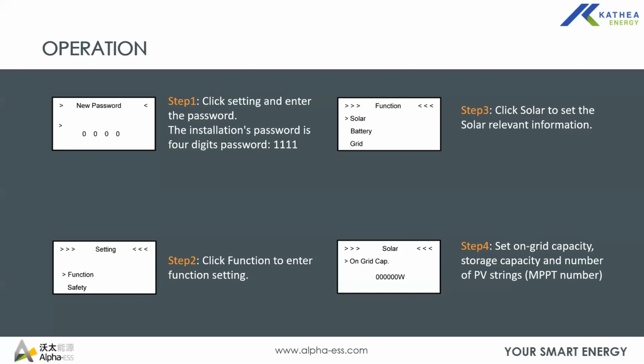Once the system is up, to access the operation functions, on the right side of the screen it has 4 buttons: escape, enter, and up and down arrows for scrolling. From the home screen, if you press enter, you scroll down to settings, and then the default password is 4 ones. Usually we don't recommend changing the password, because next time when you want to make some changes and you forgot the password, that becomes a hassle. So we prefer that you leave the installer's password as 4 ones. You just type it in, press enter, the arrow would move from password to the zeros where you need to put your password, and then you use the arrows to scroll up the numbers.